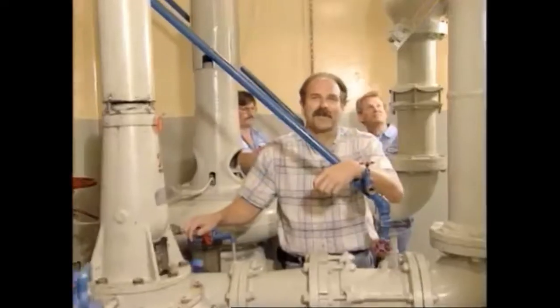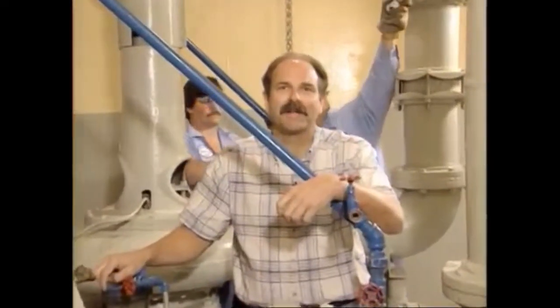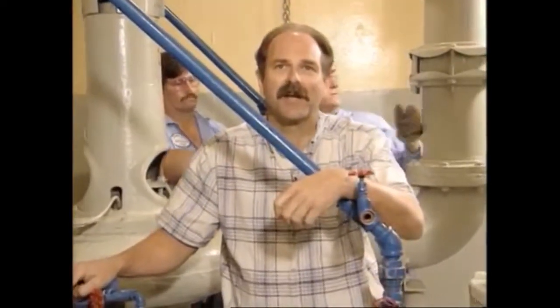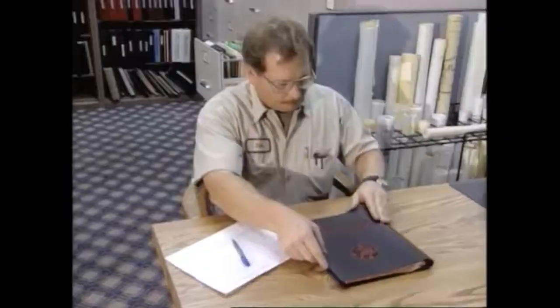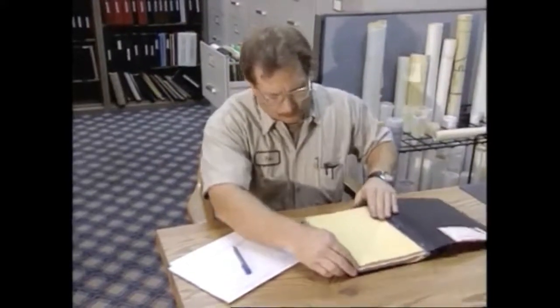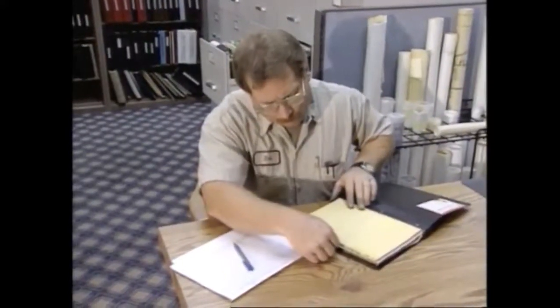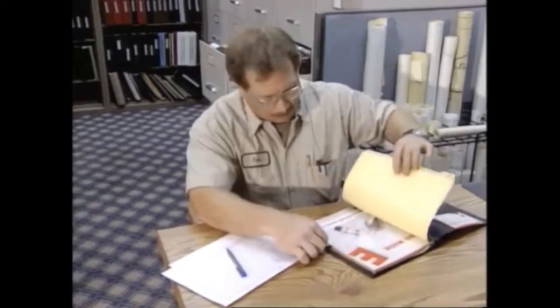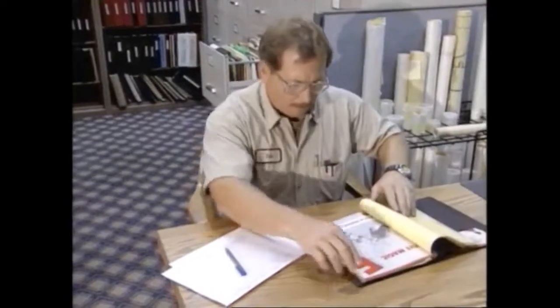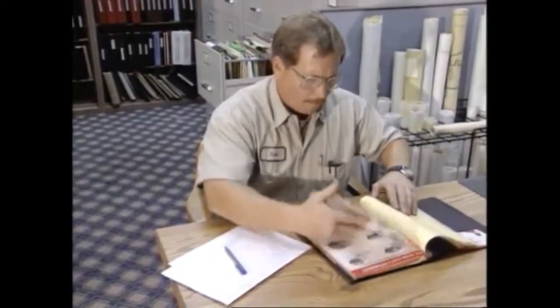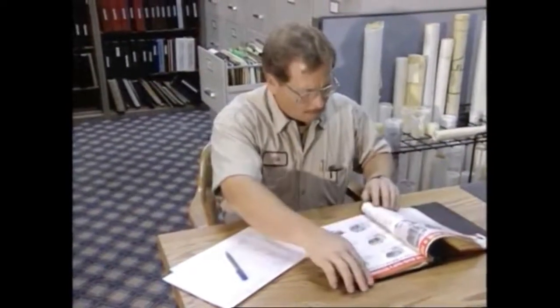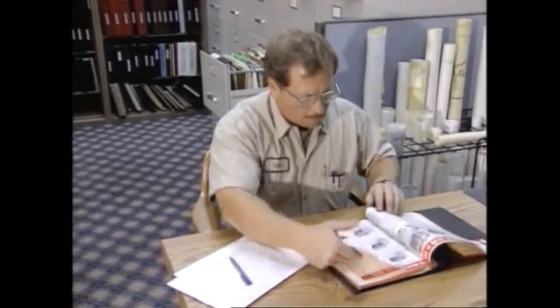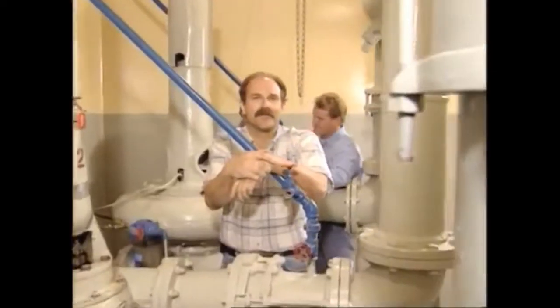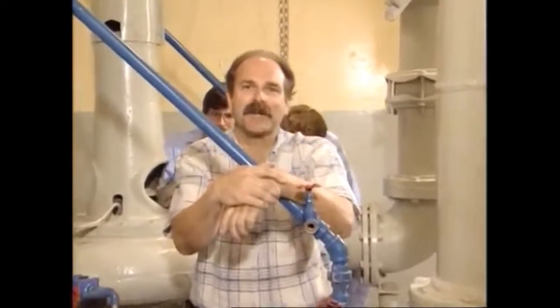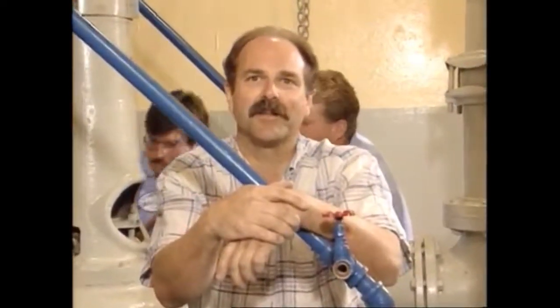Equipment manufacturers and suppliers have recommended repair and maintenance intervals for the equipment that they supply to the utility company. Usually this information is contained in a convenient binder or manual, or possibly a computer. Information includes frequency of oil changes and lubrication of bearings, types of lubricants, operating temperature ranges, pressures, flow rates, and disassembly procedures for specific equipment maintenance or parts replacement. During the first year, we need to adhere to the manufacturer's recommendations to maintain the warranty on the equipment.